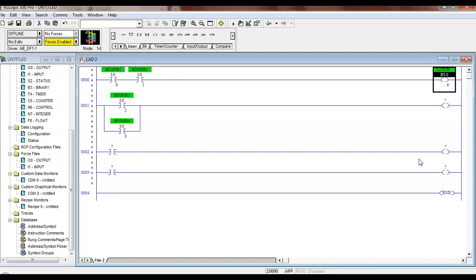It's what we call an internal coil. So this PLC's only got 6 outputs. And I'm going to use this coil for one thing. I don't want to turn something on. I'm going to use it to make a decision inside my program. So instead of sacrificing one of my outputs that's not going to turn on the light, it's not going to energize a solenoid, it's not going to start a motor, it's not going to do anything, the contacts are always going to be in my program, then we'll use what we call an internal file.